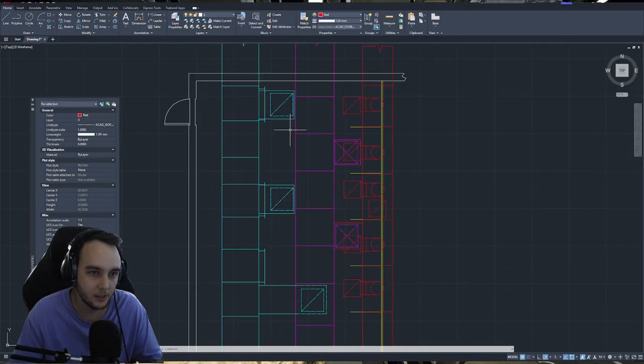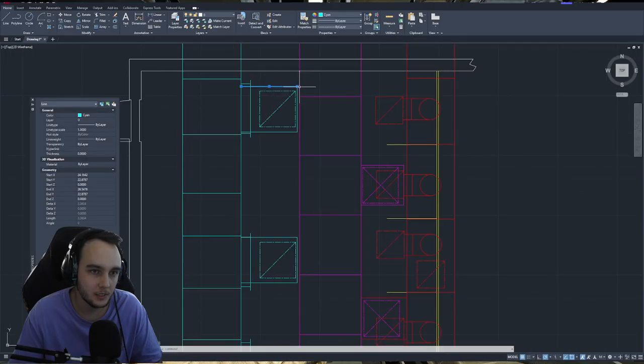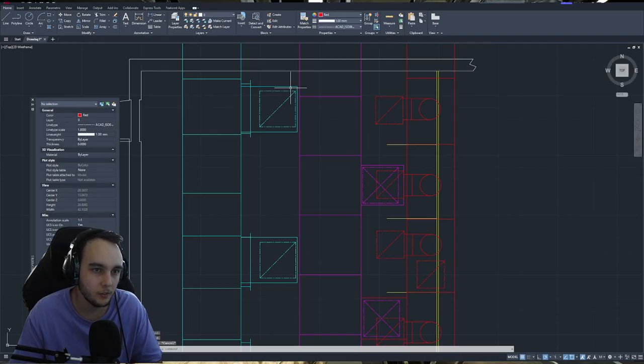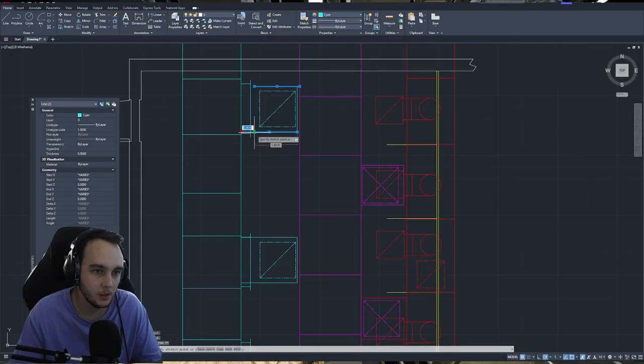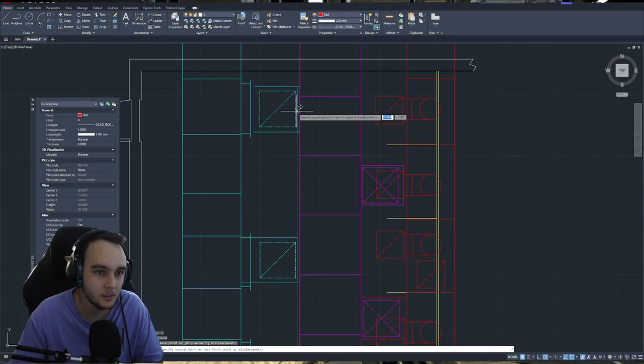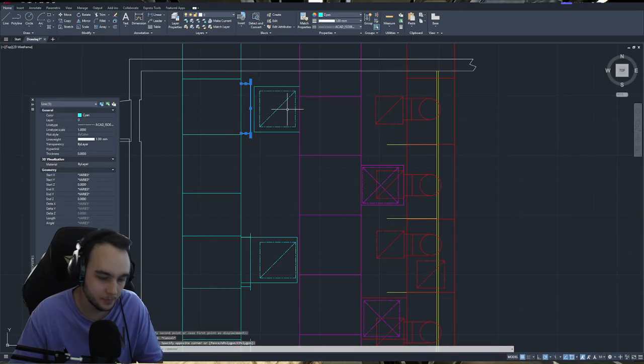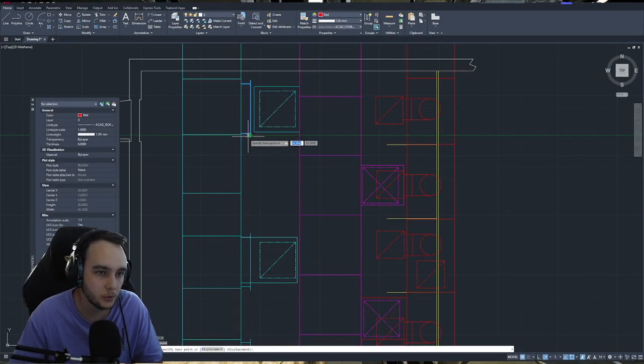So basically, if I was going to fix this, I'm not worried about where I have this, it just shows the different sections of duct. For the purpose of this, I'm not really concerned about keeping them accurate. Basically what I would do is, you've got the return duct grills, and most of the duct was going over it. So if you just take these, move them over, and then you move the return grills somewhere else.